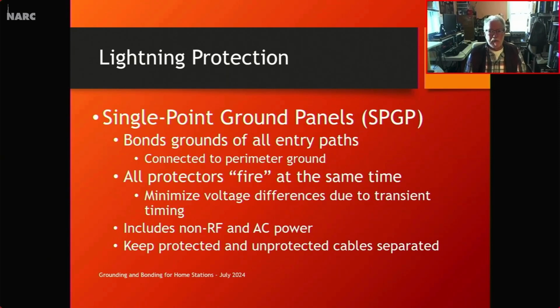Lightning transients are very short, just maybe a few milliseconds. And so it doesn't take very much time if you have your protectors separated, one over here, one over there. You'll get a really significant voltage over here with respect to this, and then later it might even reverse and go the other way. These can be kilovolts, tens of kilovolts in size. So you want all of your protectors together so that all of the systems go up and down together, and that minimizes voltage between them and the destructive currents.